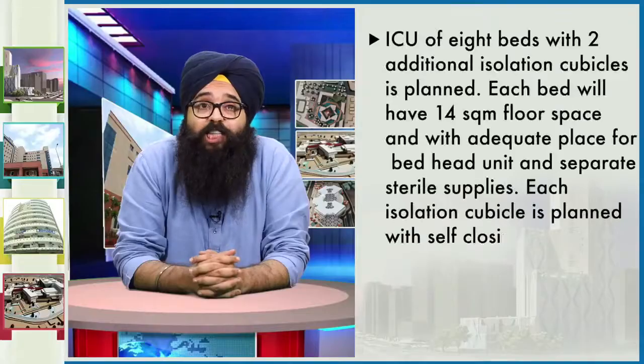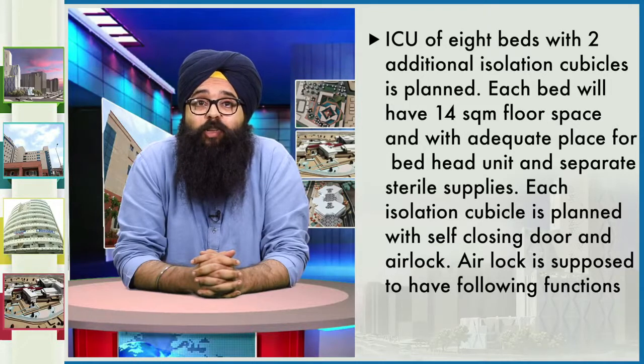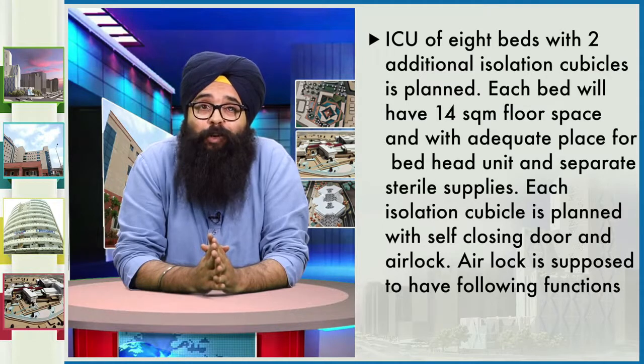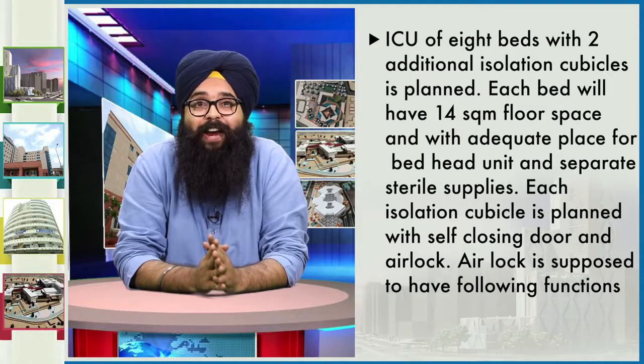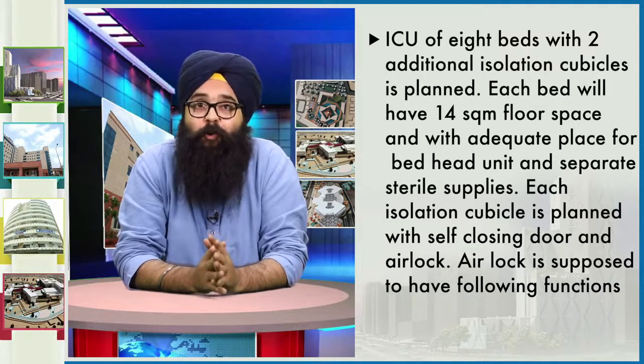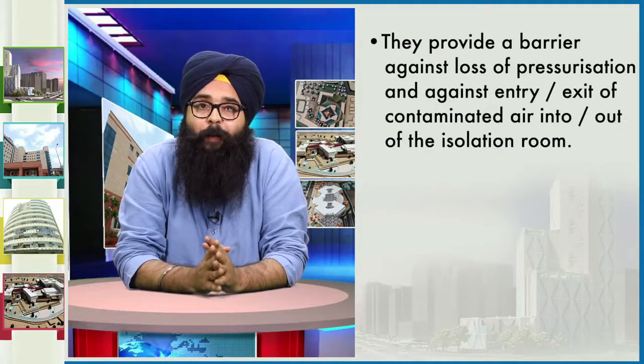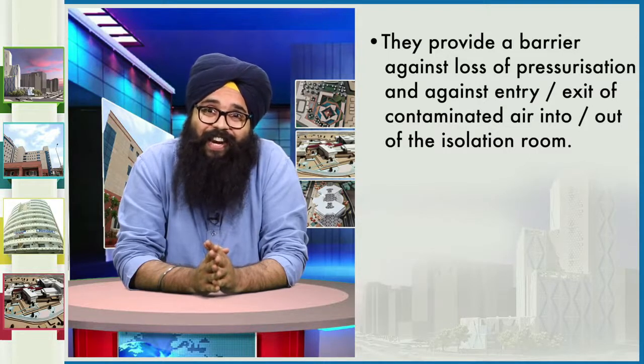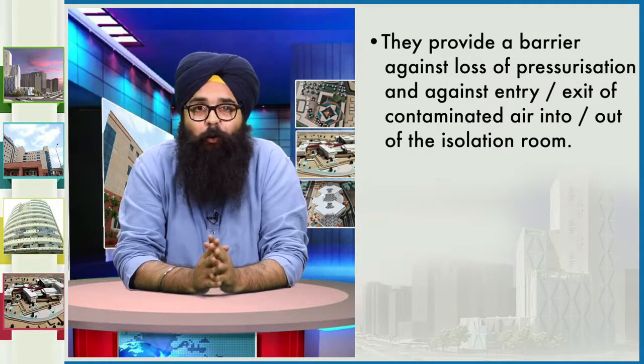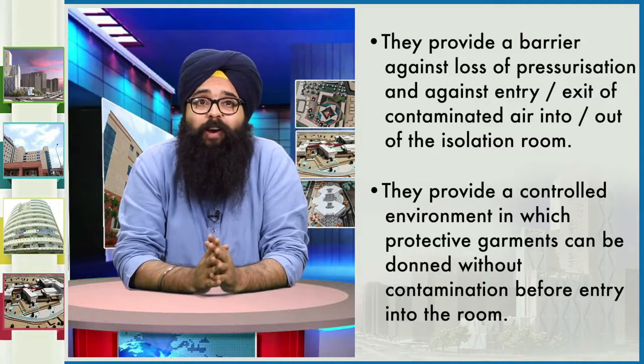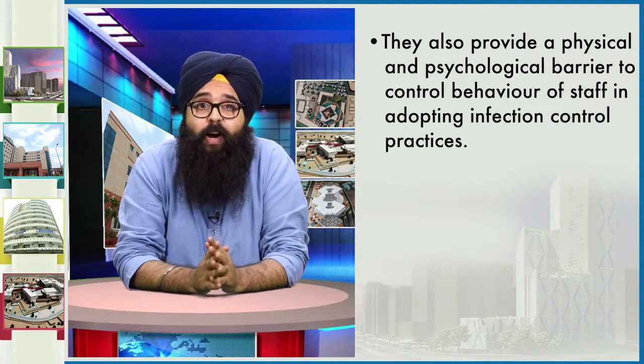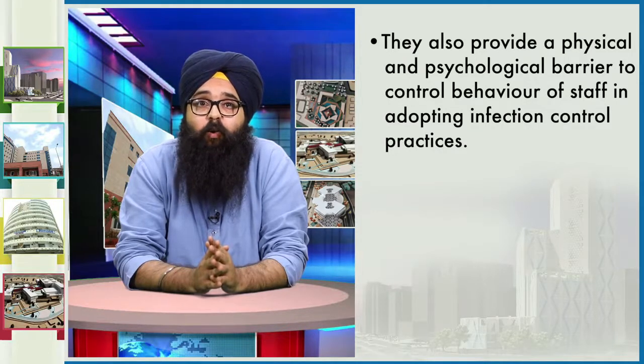As an example, an ICU of eight beds with two additional isolation cubicles is planned. Each bed has 14 square meters of floor space with adequate place for a bed head unit and separate sterile supplies. Each isolation cubicle has a self-closing door and airlock. The functions of an airlock are: to provide a barrier against loss of pressurization and against entry/exit of contaminated air; to provide a controlled environment where protective garments can be donned without contamination; and to provide a physical and psychological barrier controlling staff adoption of infection control practices.